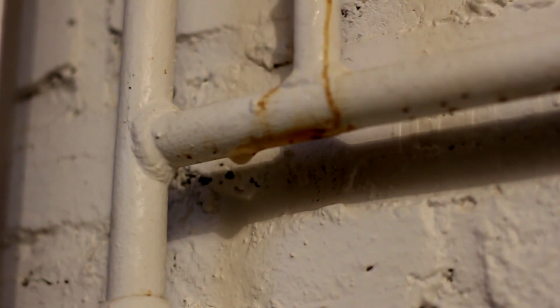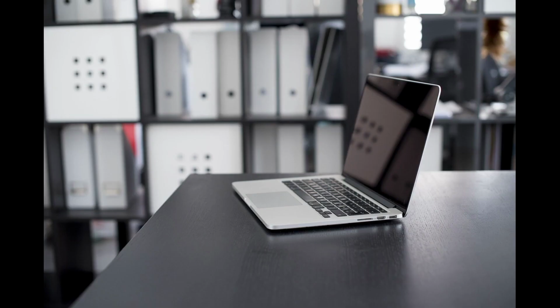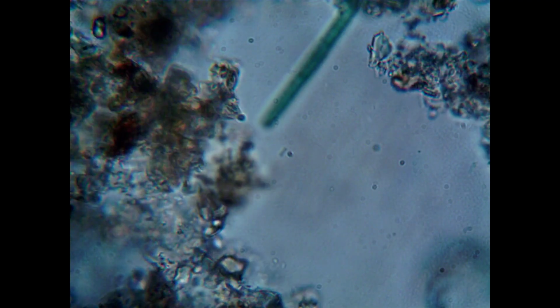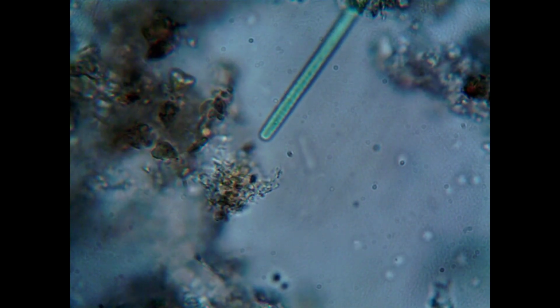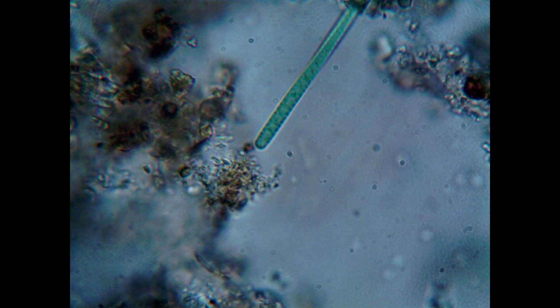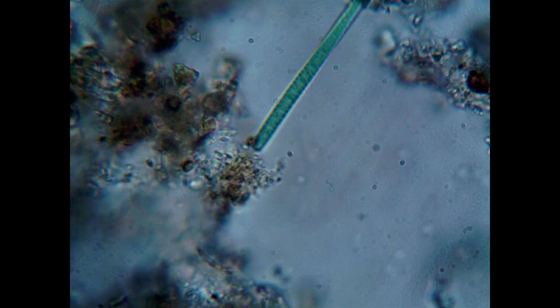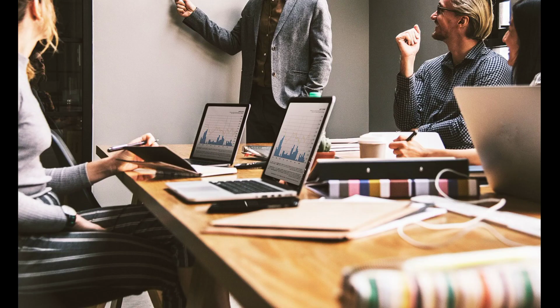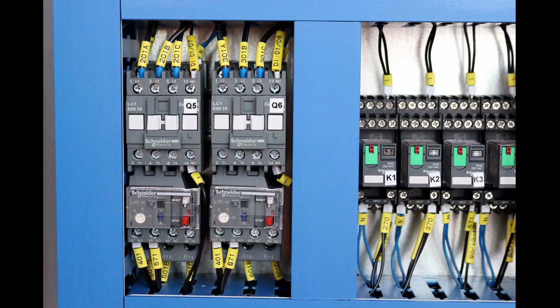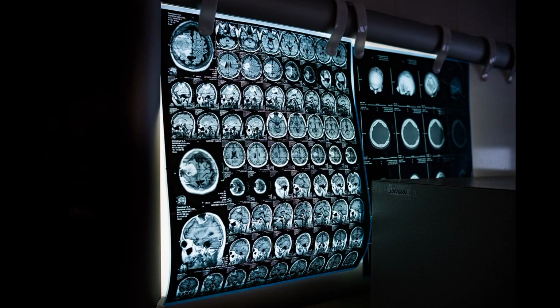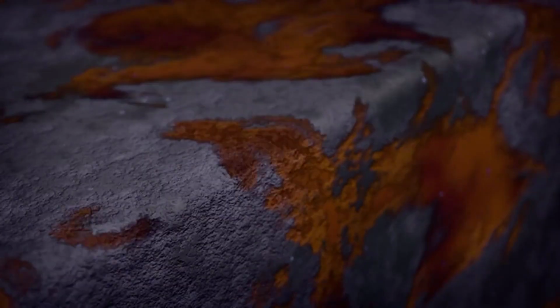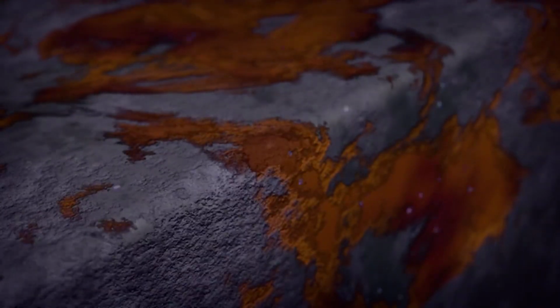Omen's insight is elegant. What if you detected bacterial growth weeks before it becomes a clog? What if you had a sensor showing exactly when to act? That's what Omen's spectrometer does. It measures the optical properties of the coolant, basically how light passes through it. Different contaminants scatter light differently. Bacteria blooms. The light signature changes. Metal particles from corrosion, different signature. Omen's algorithms instantly recognize these patterns and alert you before catastrophe strikes.